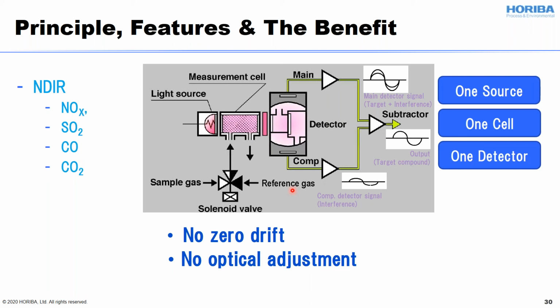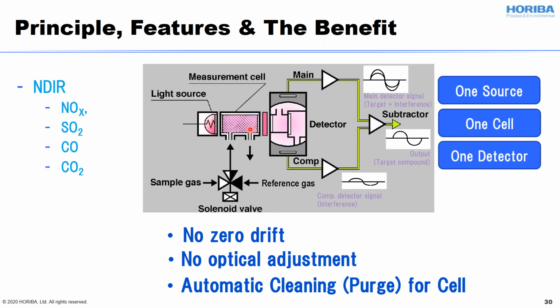And also, you have the reference gas every second, which helps to purge the inside of the cell. While you sample gas into the measurement cell, right after that, you introduce the reference gas into the cell and purge the inside. That keeps the inside of the measurement cell clean, which gives it a longer lifetime than anybody else's. So that automatic cleaning, purging of the cell, is one of the great features of this measurement unit.